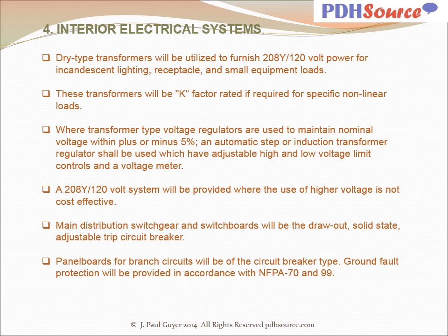These transformers will be K-factor rated if required for specific nonlinear loads, where transformer type voltage regulators are used to maintain nominal voltage within plus or minus 5%. An automatic step or induction transformer regulator shall be used, which has adjustable high and low voltage limit controls and a voltage meter. A 208Y/120 volt system will be provided where the use of higher voltage is not cost effective. Main distribution switchgear and switchboards will be the drawout solid state adjustable trip circuit breaker.